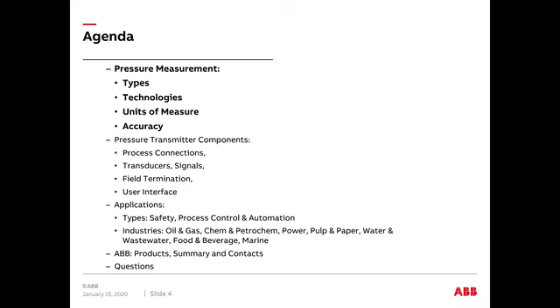So in pressure measurement, first, there are different types of pressure measurement. There's basically three different types. I've added multivariable as a fourth type. An absolute pressure transmitter is kind of like it says, it's measuring absolute, which is against a vacuum. So if there's no pressure, and you would measure atmospheric pressure, which is what a barometer is. If you have a gauge pressure, you're actually measuring the pressure against that atmospheric pressure. So if you were using a gauge pressure like a tire gauge, which is very common, you have 32 pounds per square inch of pressure. If you were measuring that same tire pressure with an absolute pressure transmitter, it would be an additional 14.5. So those are kind of the basics of the types there are.